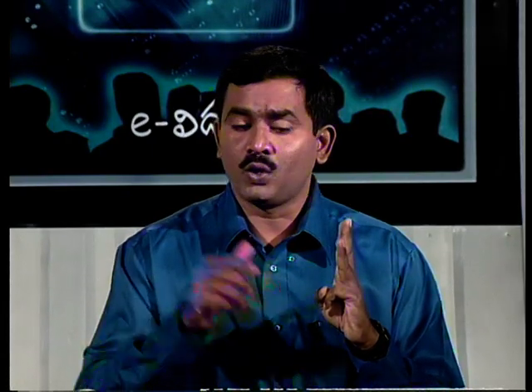Here the synchroscope is very important. For example, I have 3 units in a powerhouse. 2 are running, connected to the common bus bar grid system. Now the load demand has increased, so I want to start the third. I start it, but it is not yet connected to the common bus bar. At secondary level, we have seen the conditions to be satisfied for parallel operation. Its terminal voltage should be the same, the phase sequence should be the same, and its speed, that is the frequency, should be the same. When all these are satisfied, the synchronizing switch shows it, and you are ready to close the circuit. You can connect the incoming unit to the bus bar.